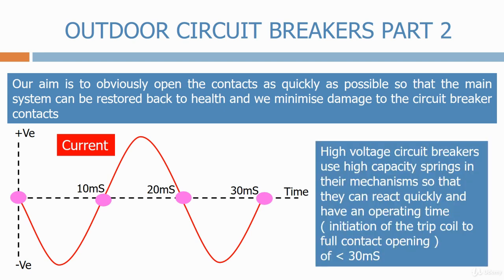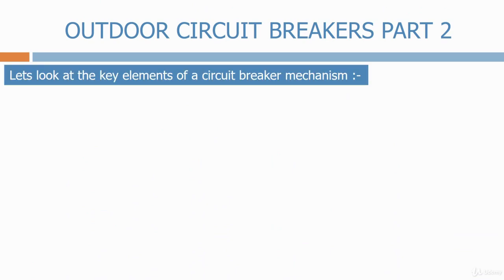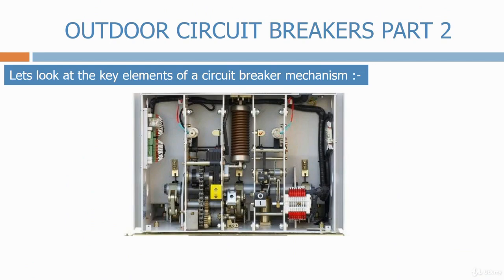High voltage circuit breakers use high capacity springs in their mechanisms so that they can react quickly and have an operating time, i.e. initiation of the trip coil to full contact opening, of less than 30 milliseconds. Let's look at the key elements of a circuit breaker mechanism. Here's a typical mechanism for a high voltage circuit breaker.